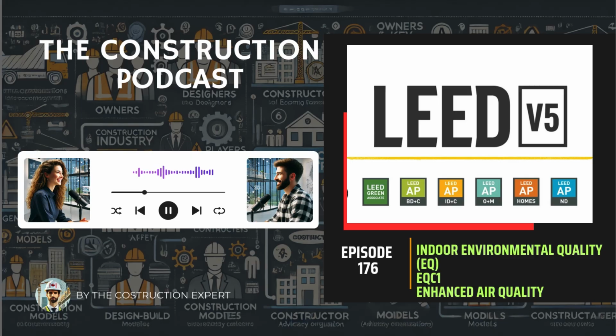So if a project is also trying hard to be energy efficient, maybe they're targeting an Energy Star rating or net zero energy, Option 1 sounds like it could be a real challenge, almost working against those goals. It becomes a serious design tension, absolutely. You are quite literally working against the energy efficiency goals by imposing this increased fan power requirement and this increased conditioning load from all that extra outside air.